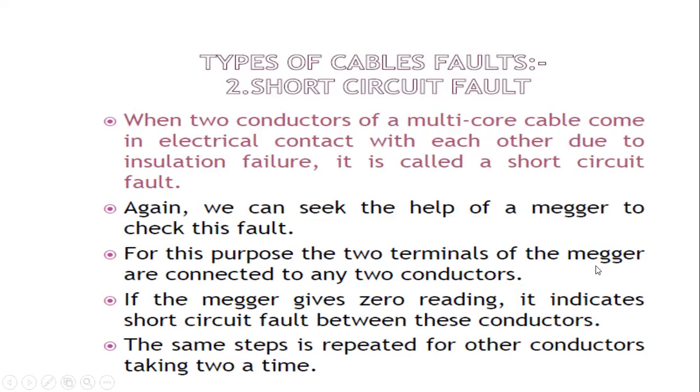For this purpose, the two terminals of the Megger are connected to any two conductors. If the Megger gives the zero reading, it indicates a short circuit fault. If the Megger gives the zero reading, then we identify that a short circuit fault has occurred in the line, between these conductors.